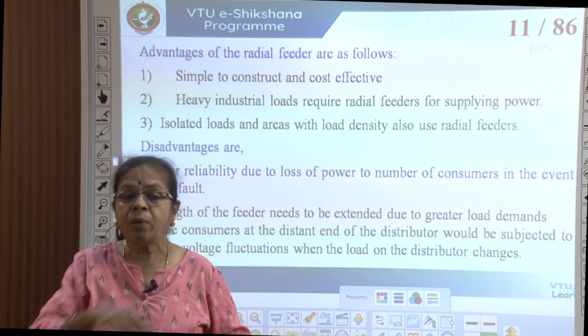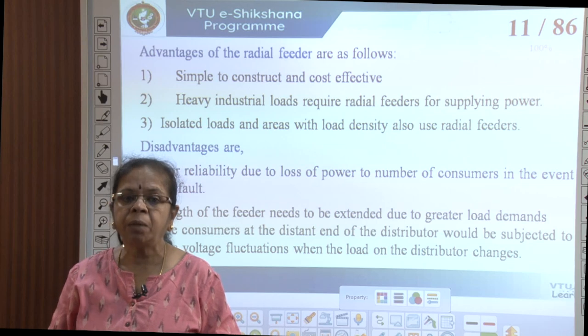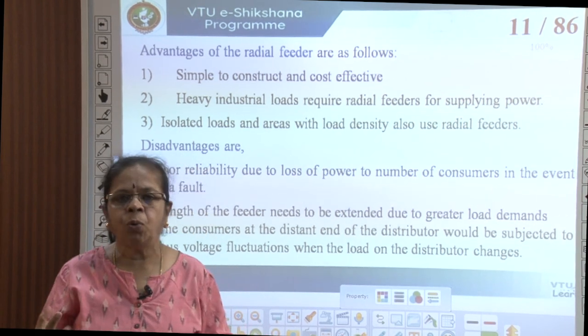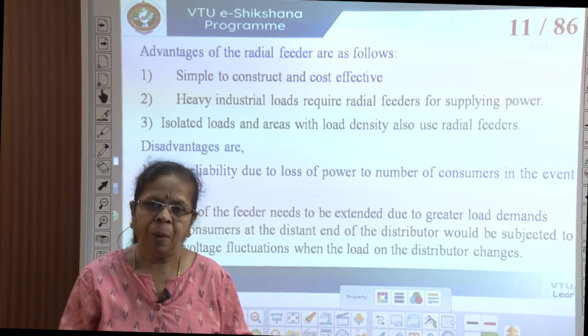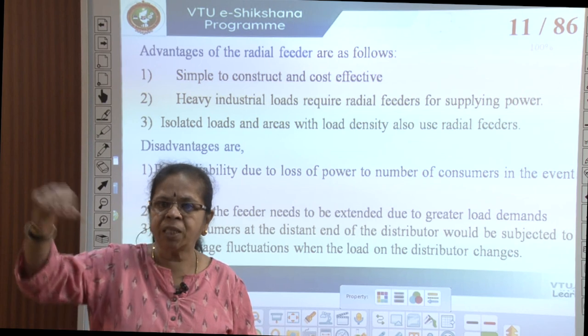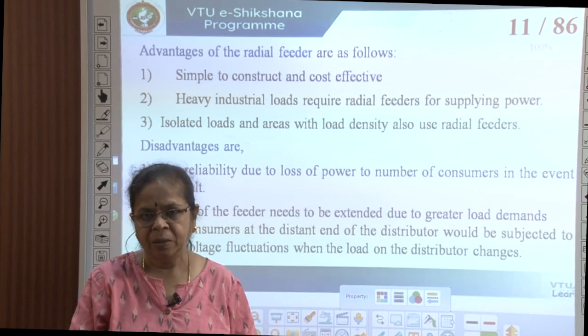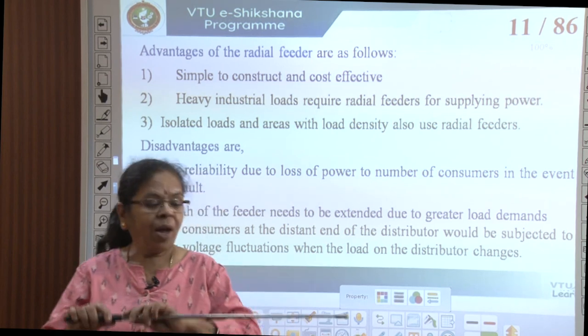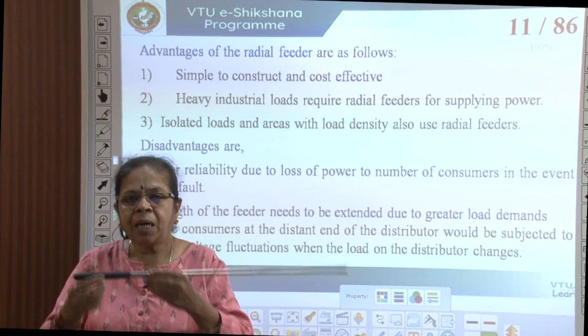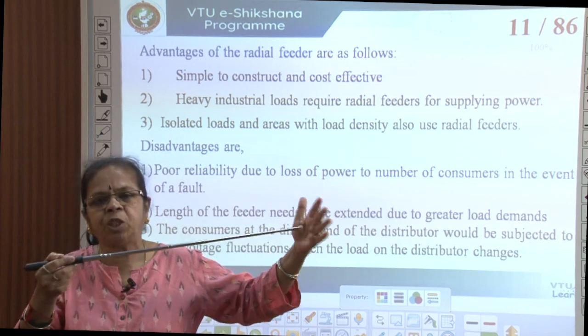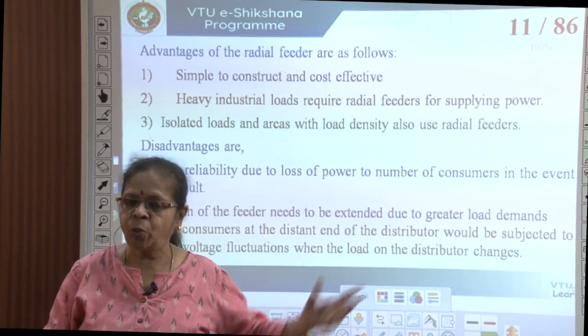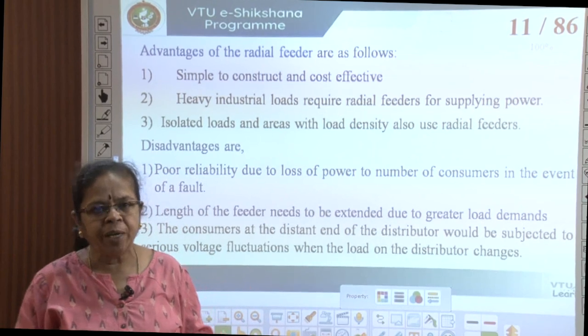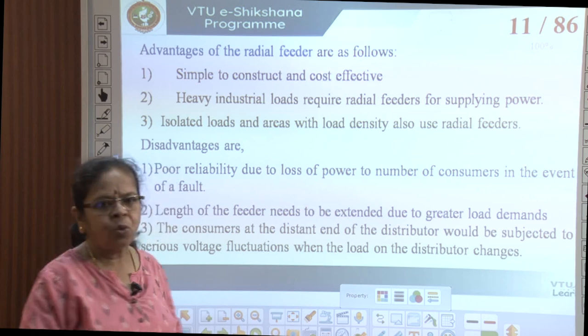In a radial feeder there are no alternate paths, so reliability is poor and there is more likelihood of consumers being without supply in the event of a fault. If the load is further away, longer feeders are needed. Consumers at the far end of the line are subjected to lesser voltages, and voltage fluctuation increases as you move away from the source. Despite these disadvantages, radial feeders are widely used because they are very easy and simple to construct.